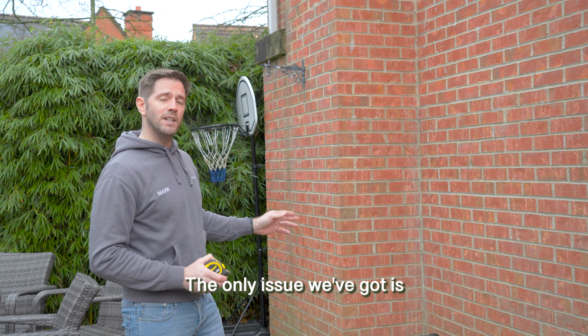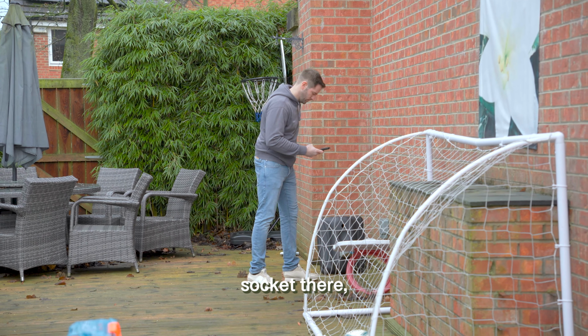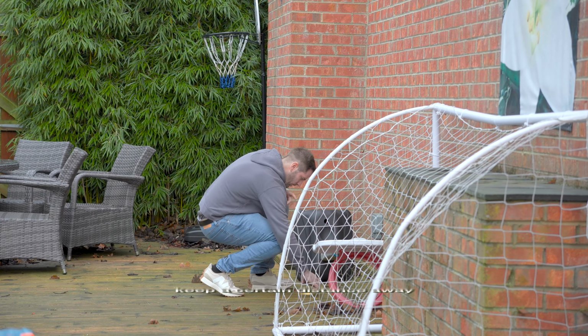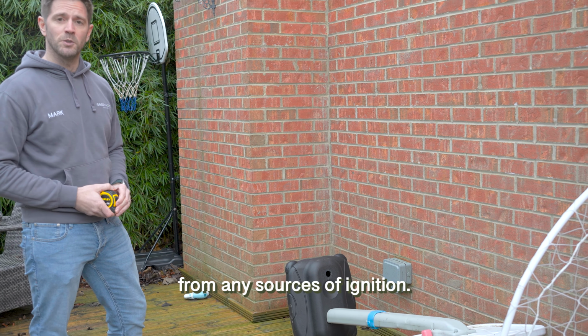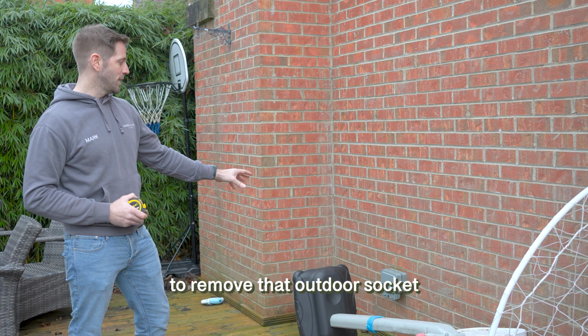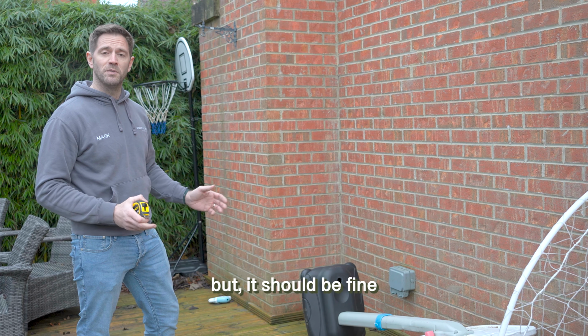The only issue we've got is that we've got an outside socket there, and with R290 heat pumps we need to keep a certain distance away from any sources of ignition. So we're going to have to remove that outdoor socket, but it should be fine to go here.